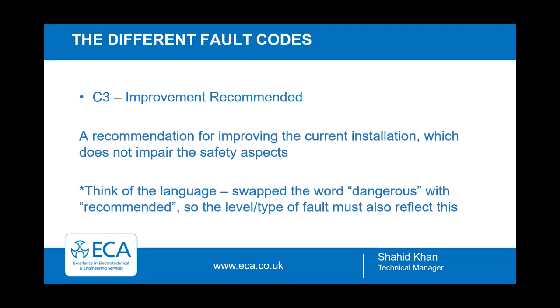If the issue is aesthetic alone, I wouldn't code the item. However, some inspectors would point to regulation 134.1.1 and emphasise the good workmanship element of that regulation to justify the code. Hence the subjective nature of periodics at times. Neither are necessarily wrong, depending on the scope of works agreed with the client.